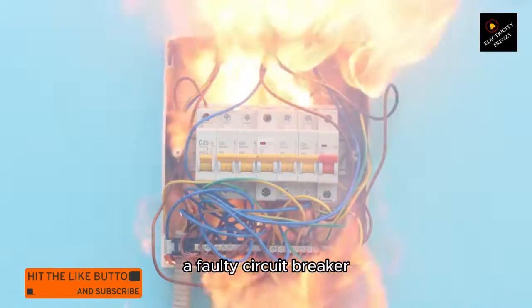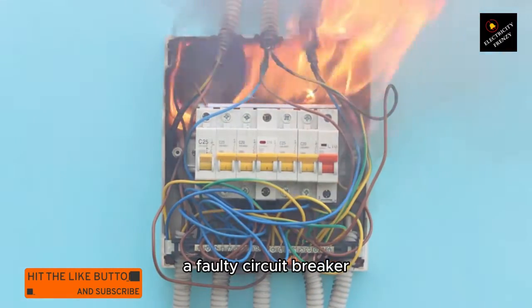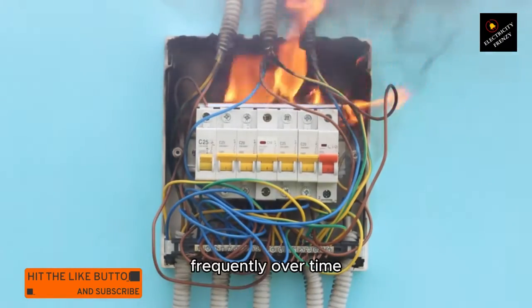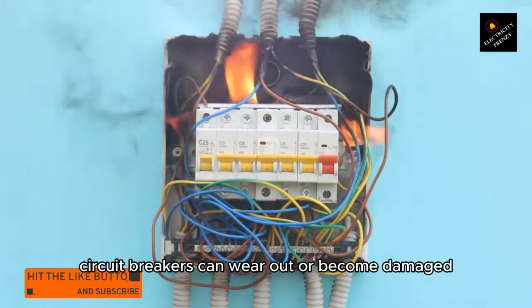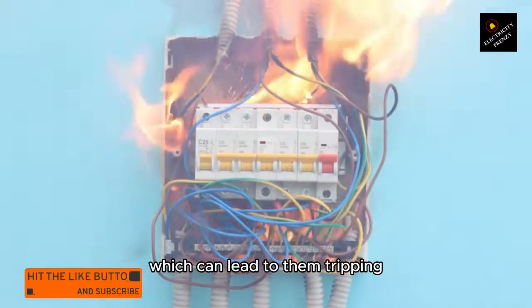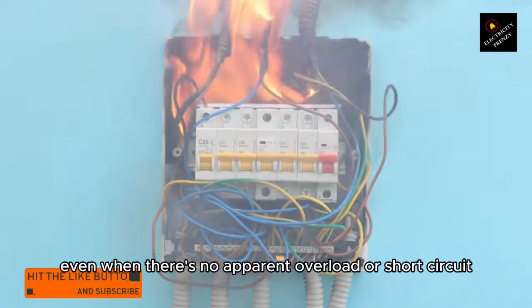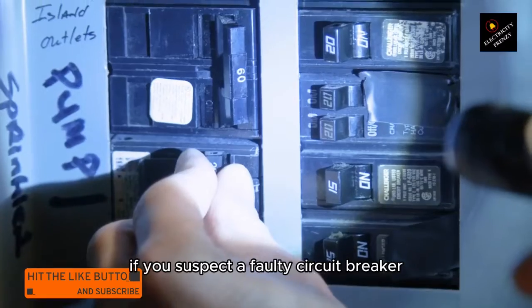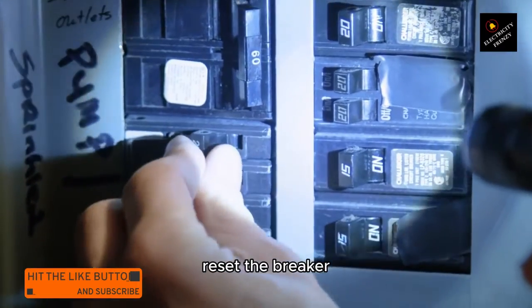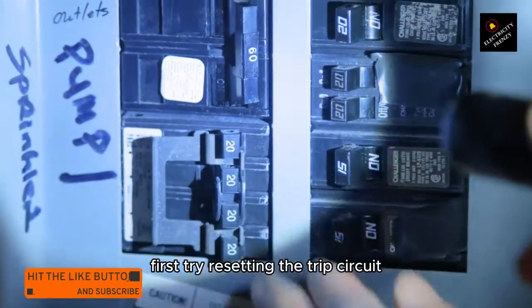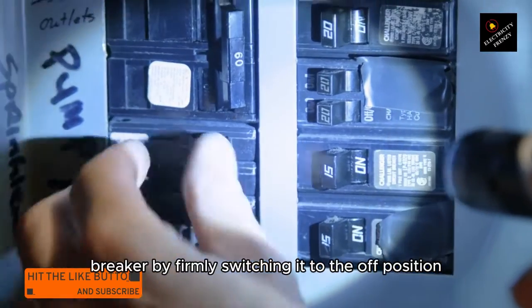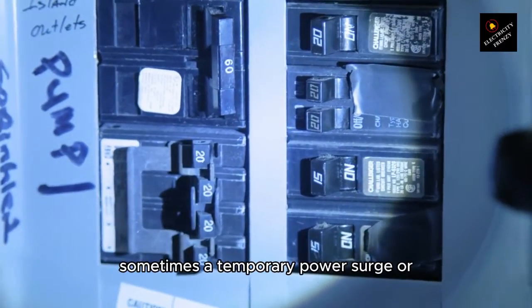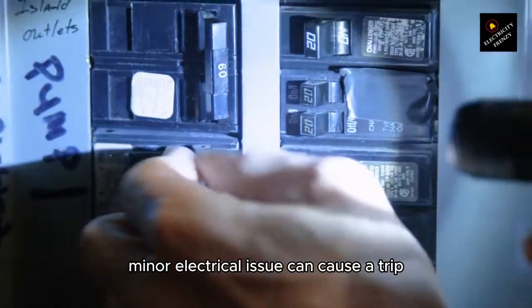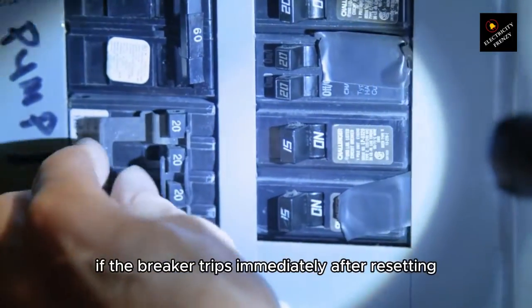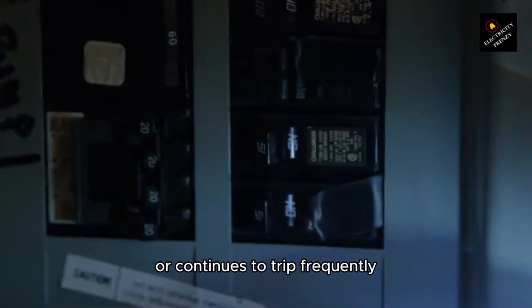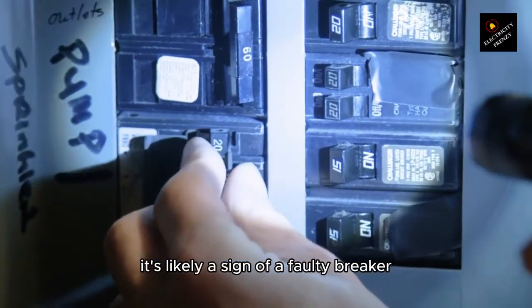A faulty circuit breaker. A faulty circuit breaker can also be a possible cause for its tripping frequently. Over time, circuit breakers can wear out or become damaged, which can lead to them tripping even when there's no apparent overload or short circuit. Here's what you can do if you suspect a faulty circuit breaker. Reset the breaker. First, try resetting the tripped circuit breaker by firmly switching it to the off position and then back to the on position. Sometimes, a temporary power surge or minor electrical issue can cause a trip. If the breaker trips immediately after resetting or continues to trip frequently, it's likely a sign of a faulty breaker.